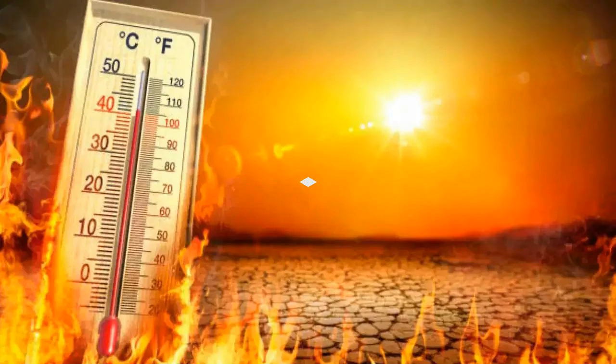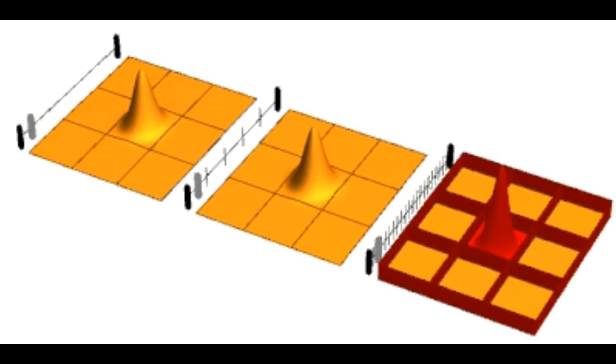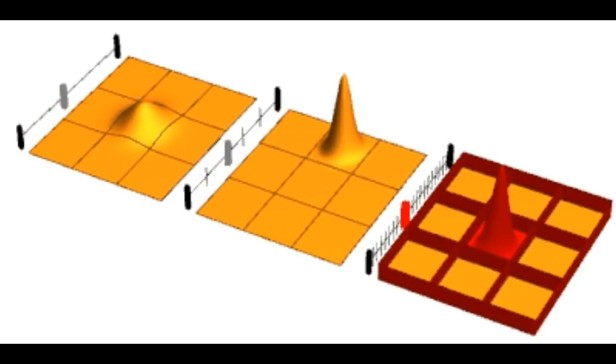Objects with an extremely high temperature result in the echo only reaching the sensor head diffusely or not at all. Environmental factors such as air turbulence can have an impact on echo quality and therefore also the measurements. The ambient temperature influence is cancelled by temperature compensation.